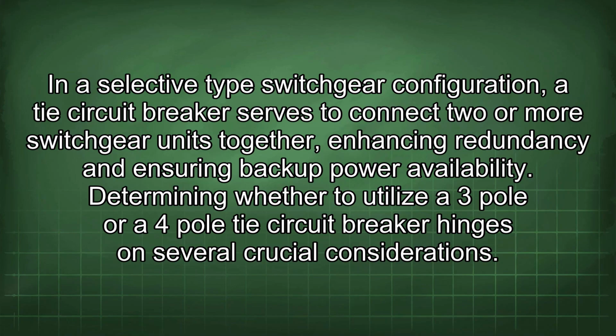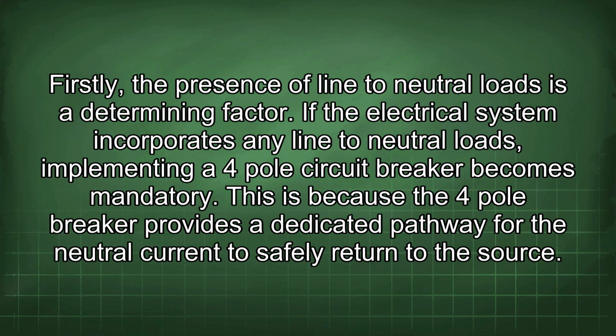In a selective type switchgear configuration, a tie circuit breaker serves to connect two or more switchgear units together, enhancing redundancy and ensuring backup power availability. Determining whether to utilize a 3-pole or 4-pole tie circuit breaker hinges on several crucial considerations. Firstly, the presence of line-to-neutral loads is a determining factor. If the electrical system incorporates any line-to-neutral loads, implementing a 4-pole circuit breaker becomes mandatory.